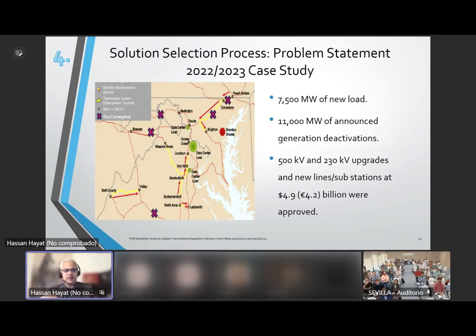Power gets rerouted. What's going on? You have huge data requirements in this part of the system, but the vast majority of the generation, the big generators, are located outside of that system. So the generators rely on wires or the transmission network to bring power from where it's produced to the areas where it's needed. But if one or more of those import paths are unavailable, the paths that remain are now constrained, no longer capable of bringing the generation to serve the load.